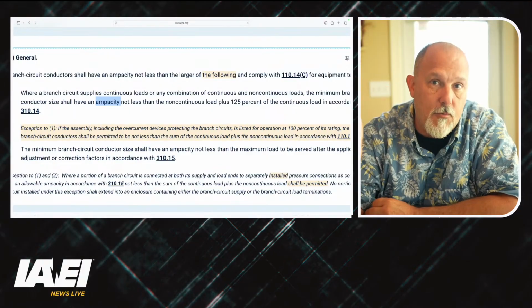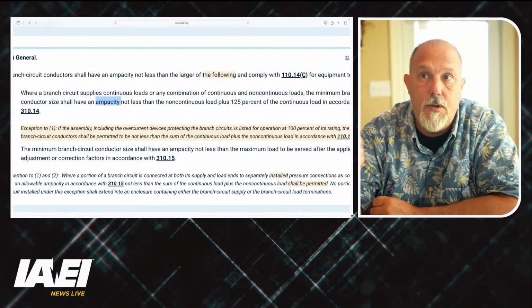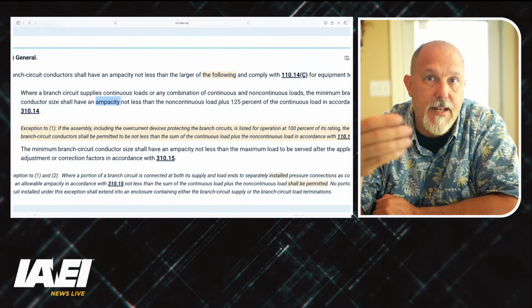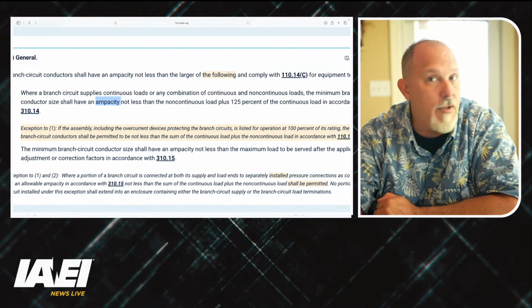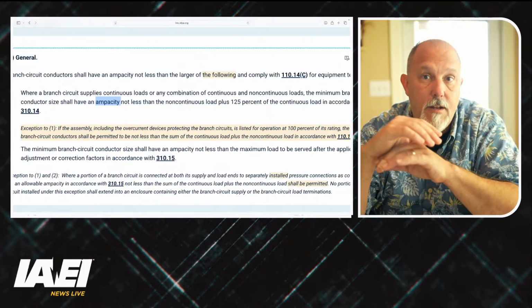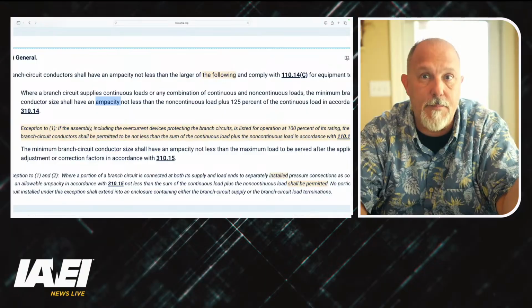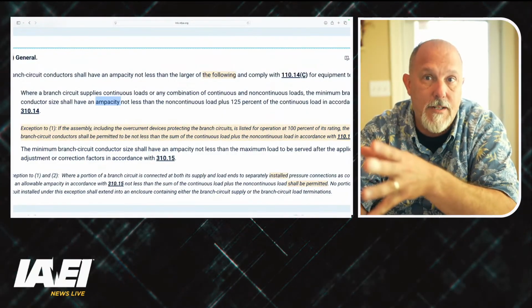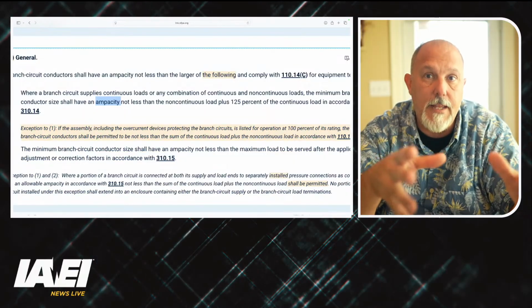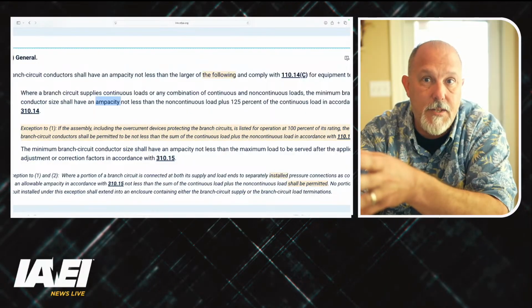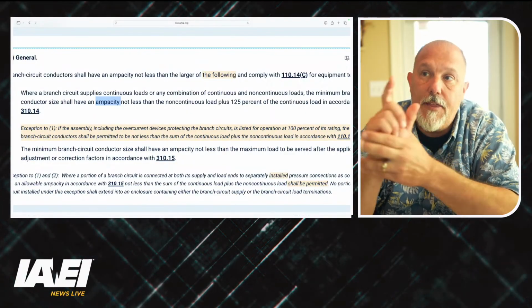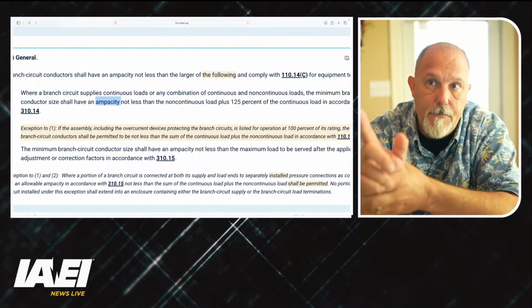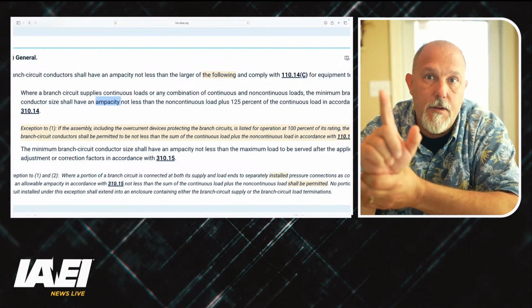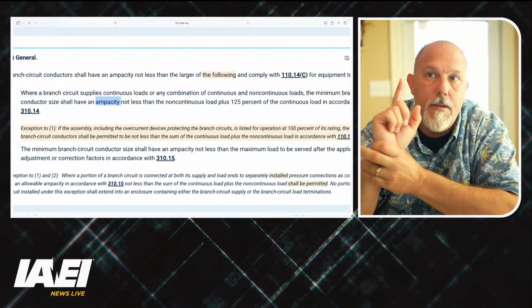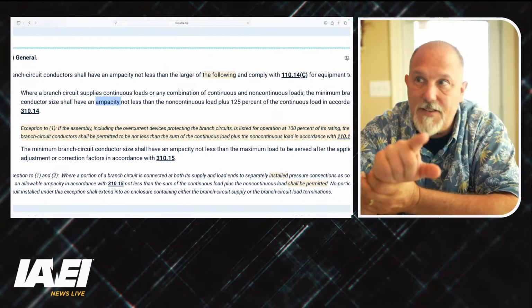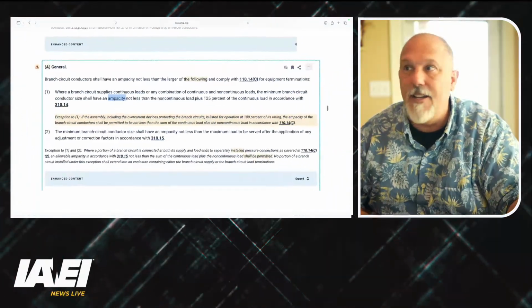So if I have 80% rated equipment, I know that I need to take 125% times the continuous plus the non-continuous, not the 125% of the non-continuous. So if I have 100 amps of continuous and 50 amps of non-continuous, I would take 100 times 1.25 and get 125, plus the 50 amps of non-continuous. And then I would add those together, and then I would go and find in Article 310 the size of conductor that would be adequate for that.